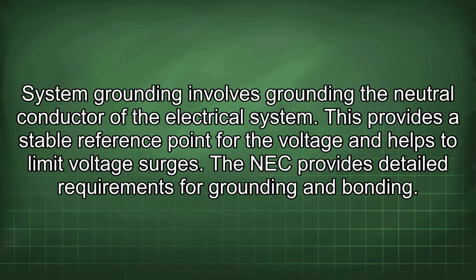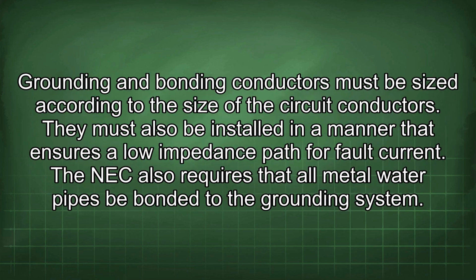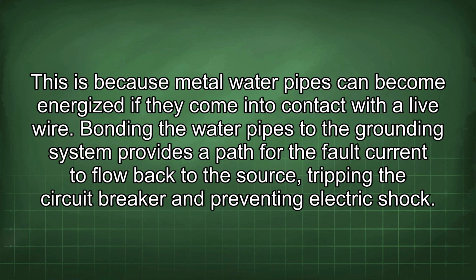The NEC provides detailed requirements for grounding and bonding. Grounding and bonding conductors must be sized according to the size of the circuit conductors. They must also be installed in a manner that ensures a low impedance path for fault current. The NEC also requires that all metal water pipes be bonded to the grounding system. This is because metal water pipes can become energized if they come into contact with a live wire. Bonding the water pipes to the grounding system provides a path for the fault current to flow back to the source, tripping the circuit breaker and preventing electric shock.